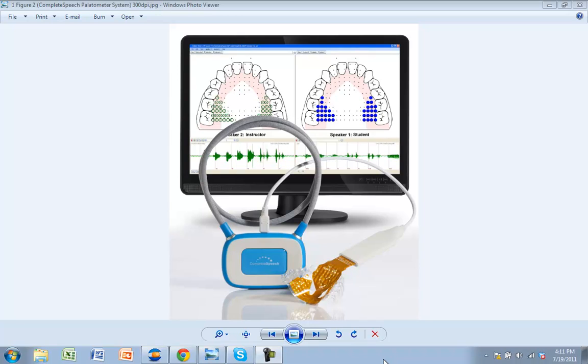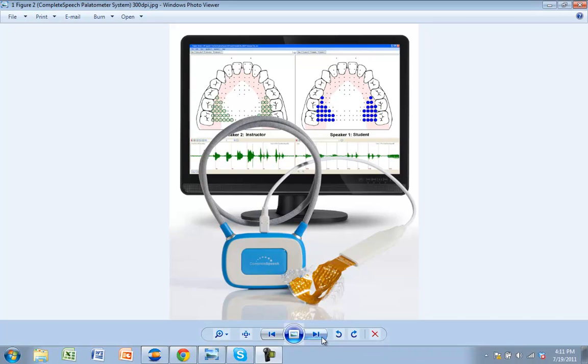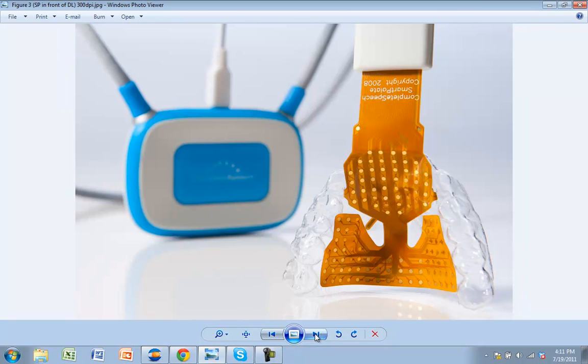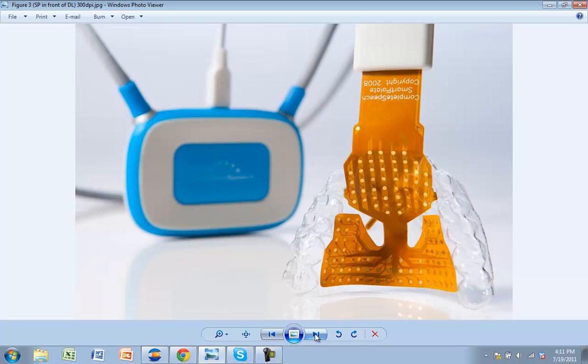In the picture on your computer screen, you see the PalateView software on the monitor in the back, and in the front you see the data link and the SmartPalate. The SmartPalate is a thin mouthpiece that minimizes the effect on speech clarity. The data link has a magnetic lanyard making it easy to put on and take off. The SmartPalate plugs into the top of the data link, and on the SmartPalate itself you'll find 124 sensors, making it extremely accurate when measuring tongue-to-palate contact during speech.